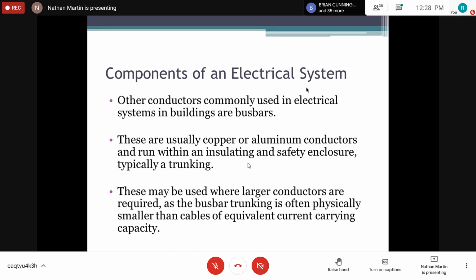No, rather than have large cables distributing power to different sub panels, you might have a bus bar setup, right? And typically, what it is being used for in today's environment is apartment complexes. Now, in an apartment complex, remember you're going to have several meters, because you have different residents. One way is to create what is known as a bus bar chamber. The bus bar chamber is so designed that you have copper bars running from one point to the next that are insulated from touching the metal enclosure, right? So it's in an enclosure like a panel box, but much larger than the panel box, because we're talking about probably 10 meters, probably 15 meters, right?